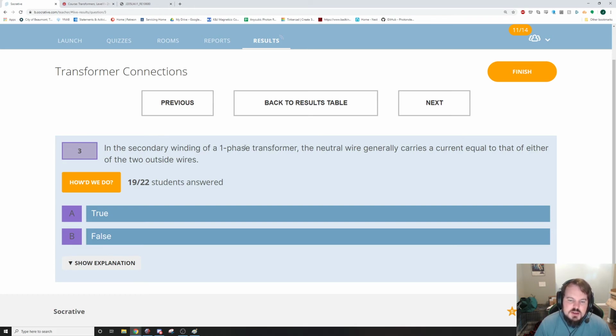The secondary winding of a single-phase transformer: the neutral wire generally carries a current equal to that of either of the two outside wires. So the neutral wire will carry the difference of the two outside wires, so this one will be false.